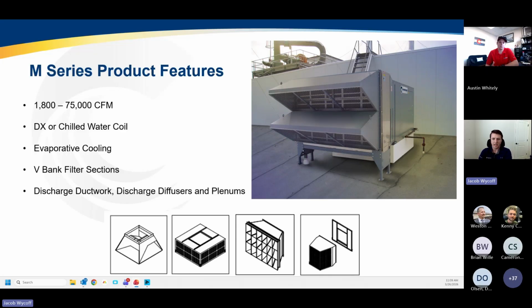So evaporative cooling is a great option, especially whenever you're applying these in your more mild climates. For these 100% outside air units, they can provide a huge amount of relief for the people or processes that are occurring in the space. We also offer filtration on these units, both in the intake hoods or as a separate V-bank filter section. These are 100% outside air units, so typically minimal filtration is required. But for those applications that call for filtration, we can offer all the way up to MERV 13 as a selectable option.